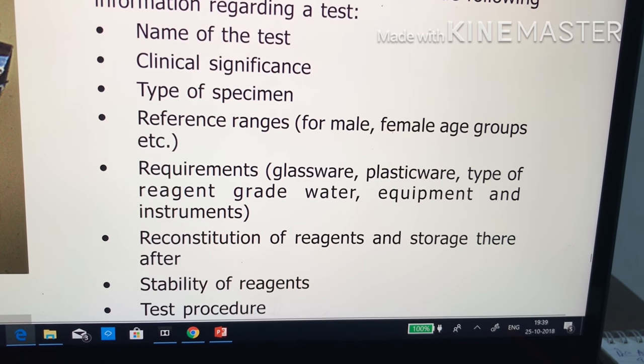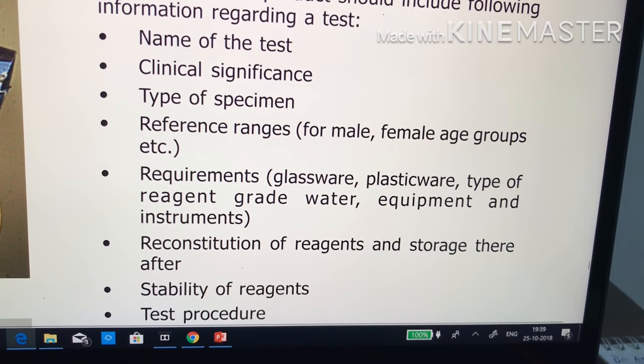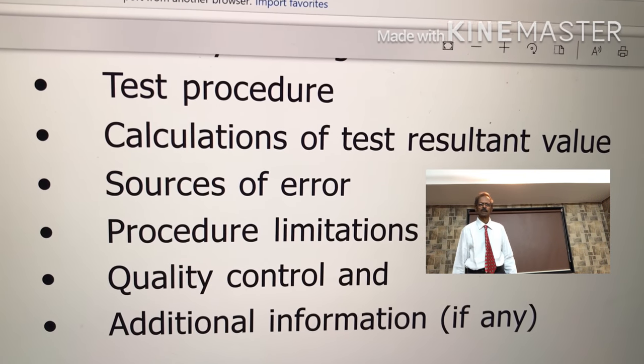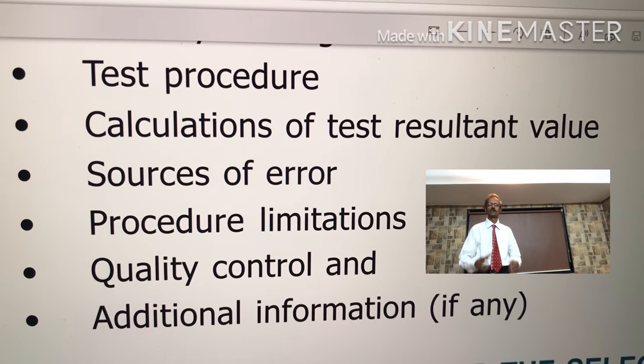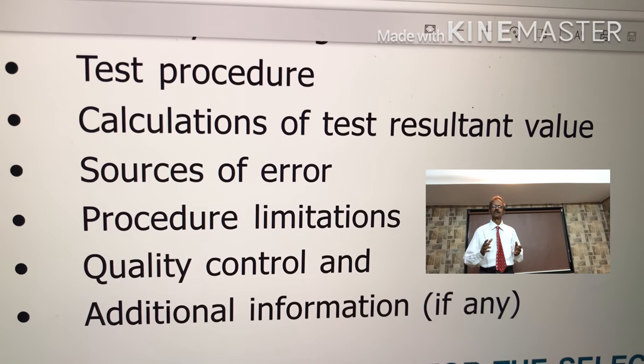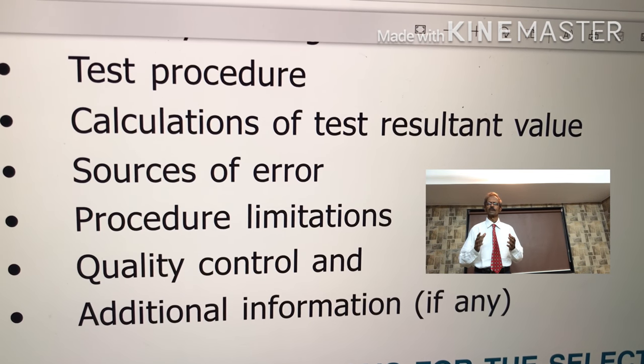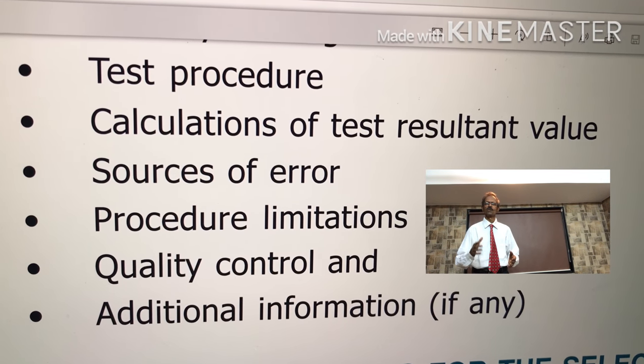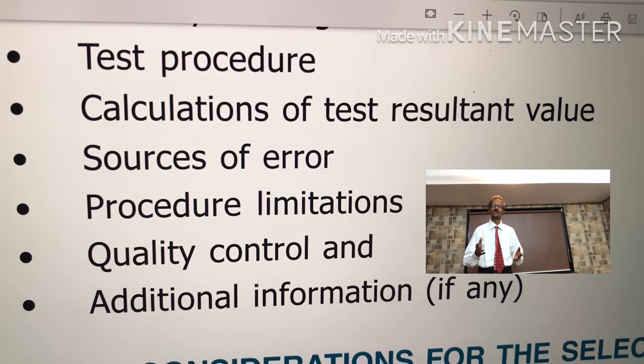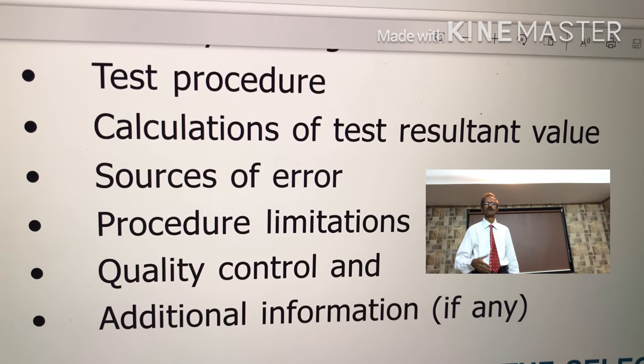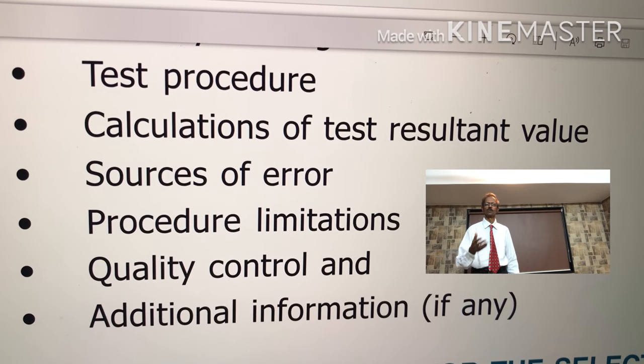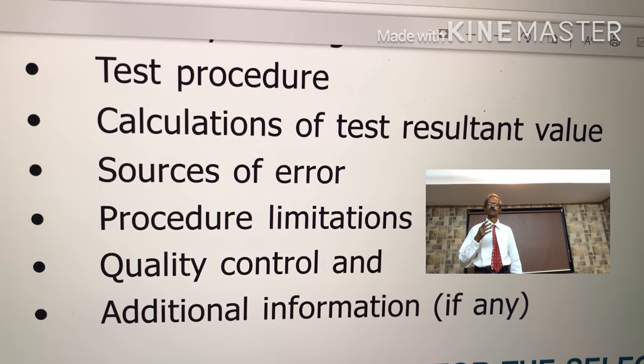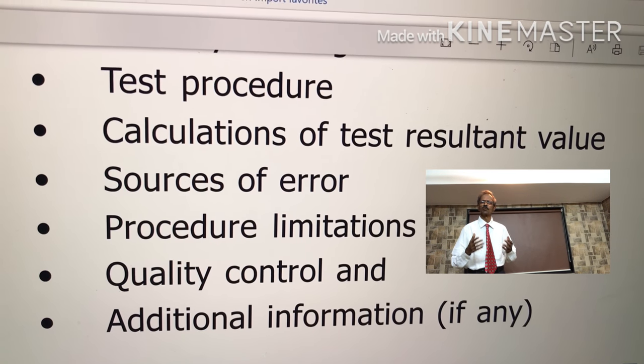That means at 0 to 4 degrees, or 2 to 8 degrees, or at room temperature — how long the reagents will be stable. Next is the test procedure: the kit literature gives you information on the test procedure, meaning the SOP, standard operation procedure — very important. And then how to calculate test results. Then sources of error — that means if the sample is hemolyzed or if bilirubin concentration is high in the sample, what will happen. Also procedure limitations: if you get very high values, the kit will indicate at what stage you are supposed to dilute the sample and repeat the test. Also information regarding quality control measures and any additional information.